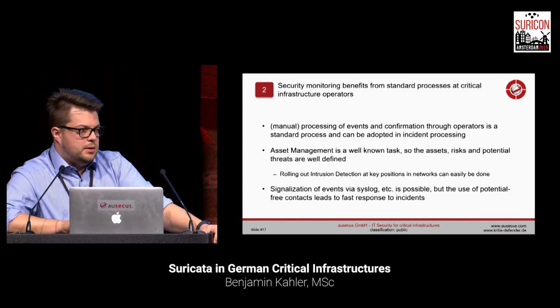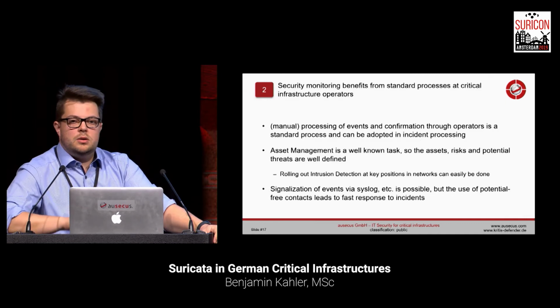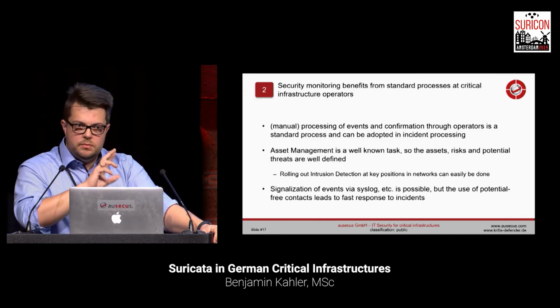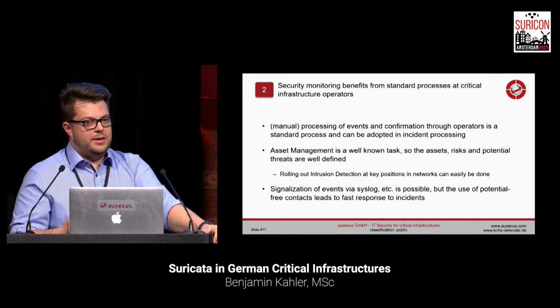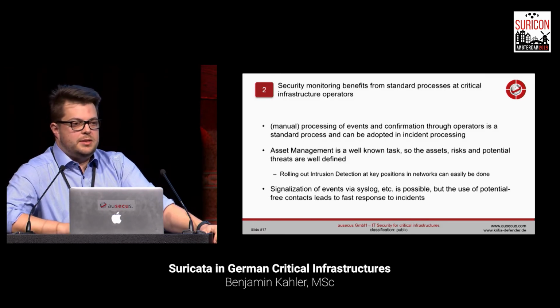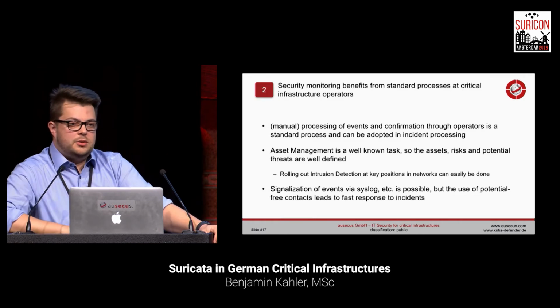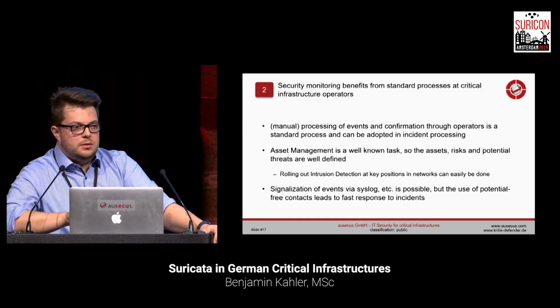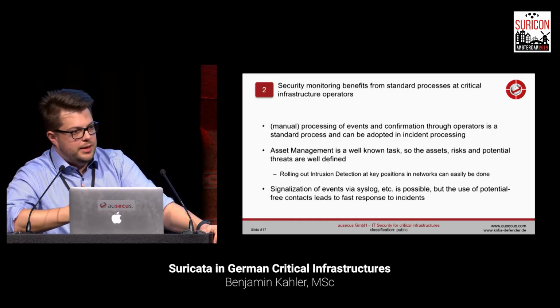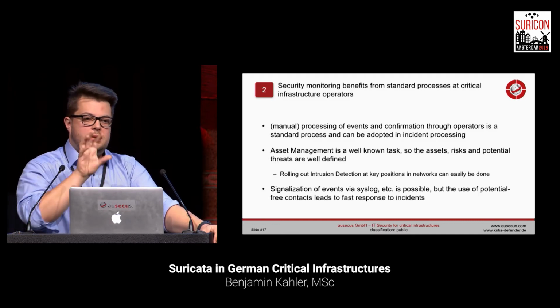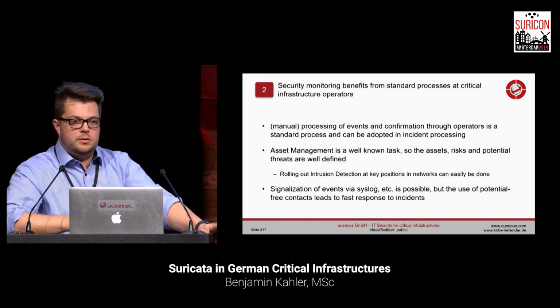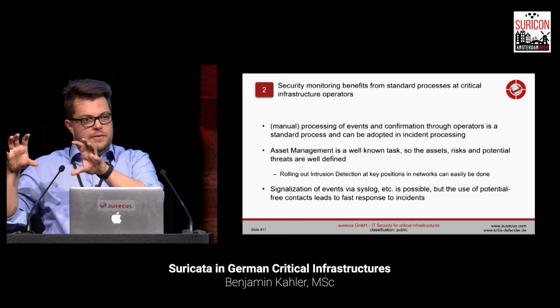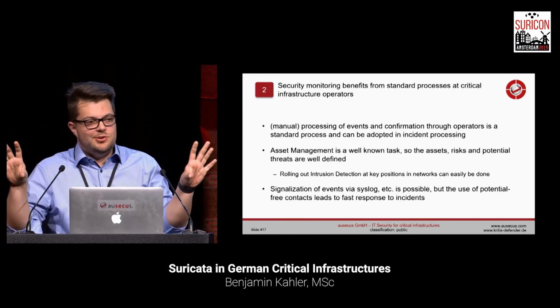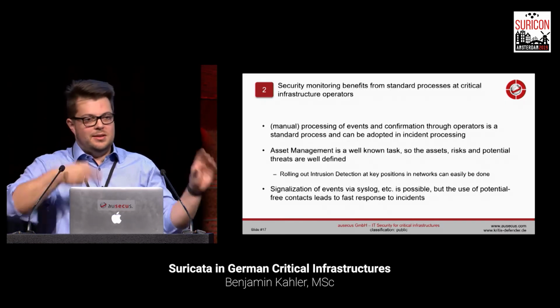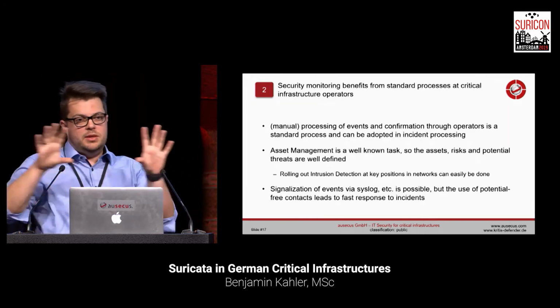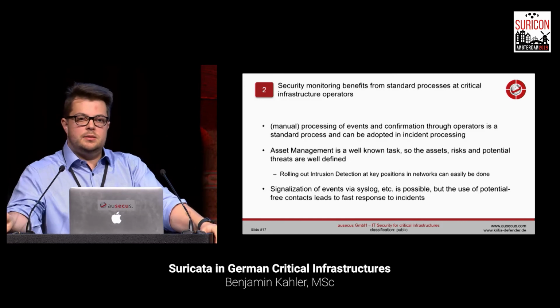So the KRITIS Defender appliance has the possibility to trigger alarms, warnings and infos over these potential-free contacts, an analog way of data communication, because our customers are using systems which process these events. They can put these potential-free contacts on one of their RTUs or one of their PLCs and report it to the main SCADA system. So we have an interconnection between KRITIS Defender and the SCADA system, but there's no TCP/IP interconnection. It's an interconnection over analog 2 wires. So the security of the SCADA system and the KRITIS Defender isn't affected if either side has a security flaw.